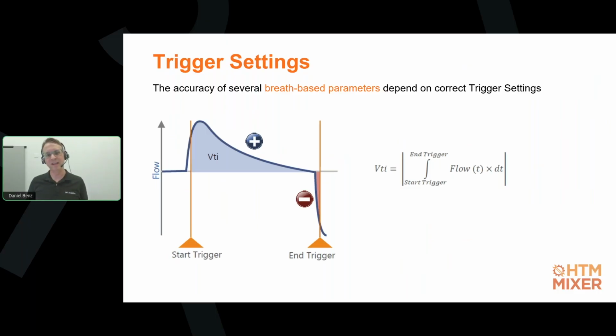But even if our analyzer is triggering, inappropriately set triggers for our specific application can also have an impact on the accuracy of the calculated breath-based parameters. For example, the inspiratory tidal volume is calculated by the analyzer by mathematically integrating the flow from the start trigger to the end trigger of an inspiration phase. Think of it as this flow waveform, where our volume is the area underneath the curve, which is shaded here.